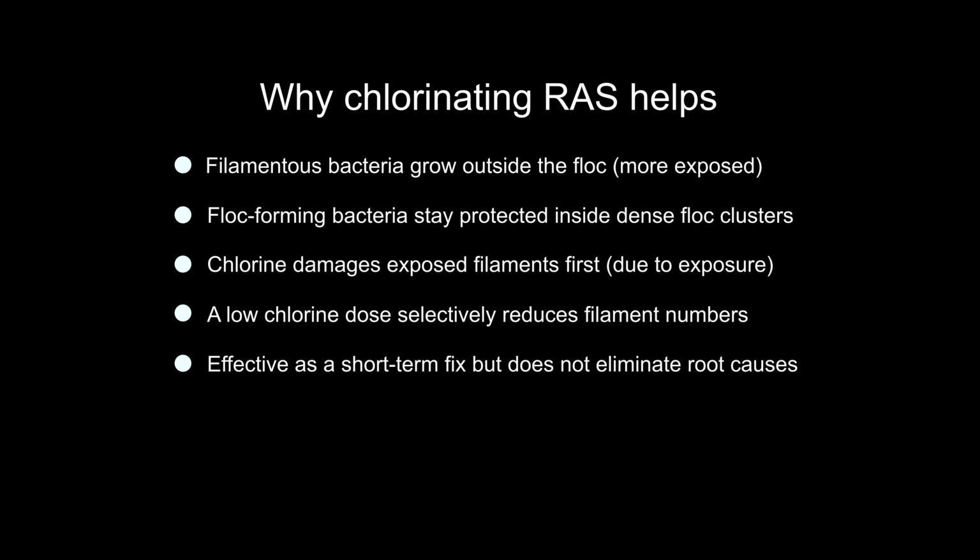The dose of chlorine should be low so that it doesn't penetrate deep enough to kill the good bacteria in the floc. It's a matter of surface area. The chlorine prunes off the bad stuff without harming the good core of our biomass. However, it's important to understand that chlorination is just a band-aid, a short-term fix to get your settling back under control so you don't violate your permit.